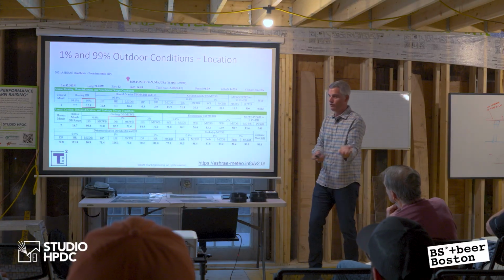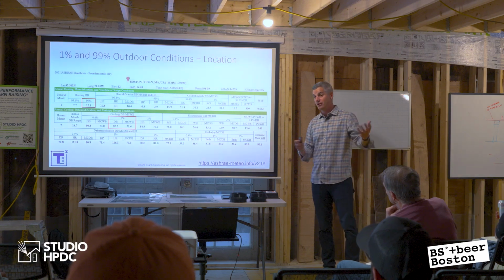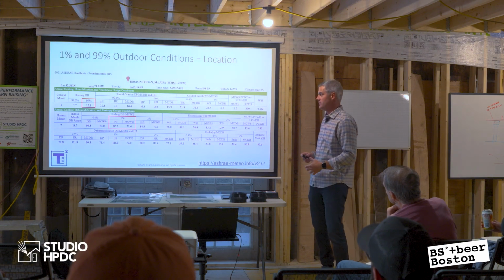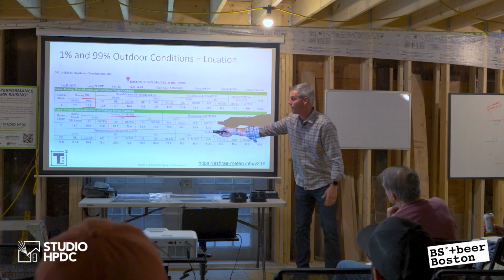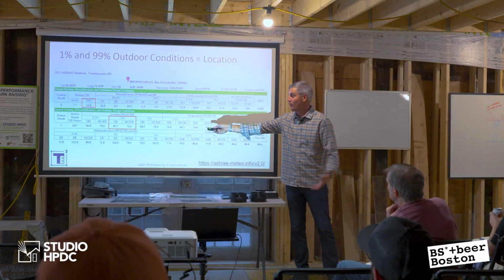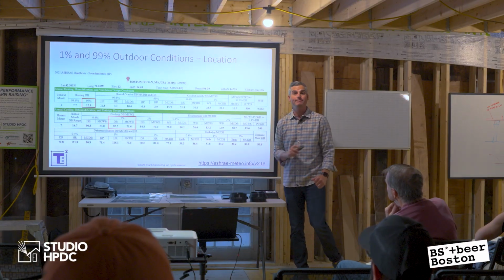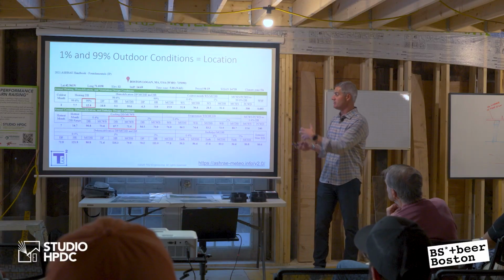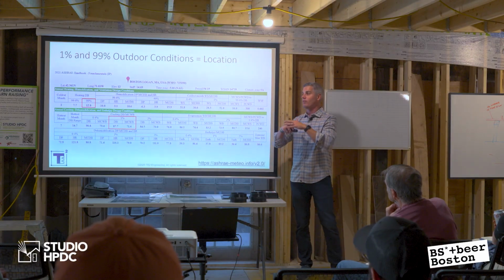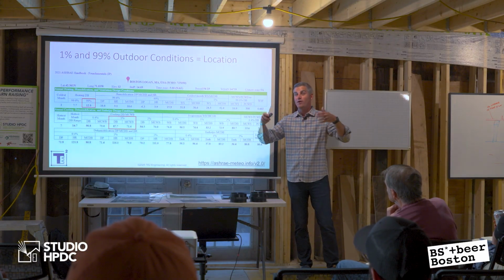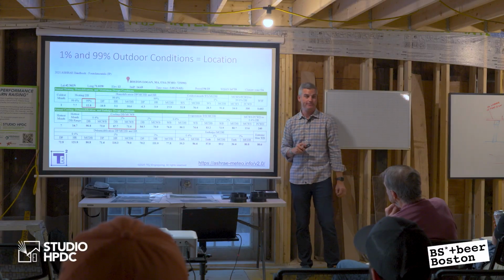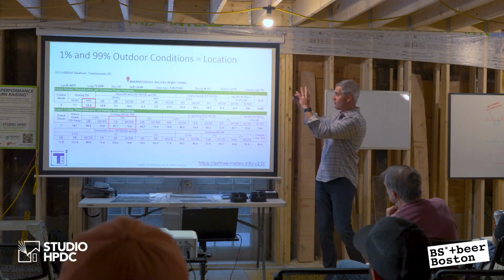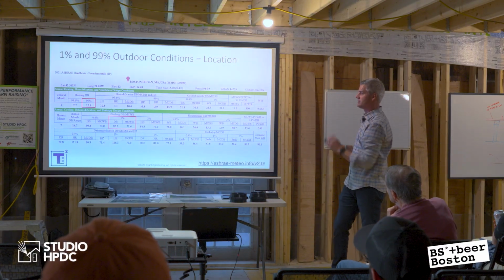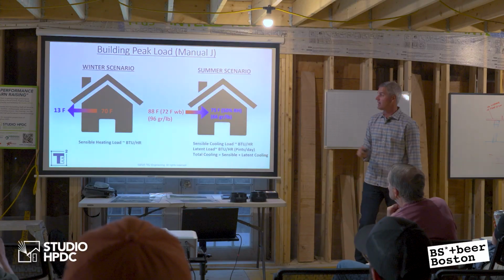If you want to play it safe, of course, you can use a different, higher, more conservative design condition. You could go to the 0.4 condition, which means 0.4% of the time you're above it, 90.8. And you can even look at the mean extremes, which are published here, of what it's been over the last 10, 20, 30, 40, 50 years. So I just want to give everyone an understanding of what these design conditions and snapshots are. And this is what it looks like.